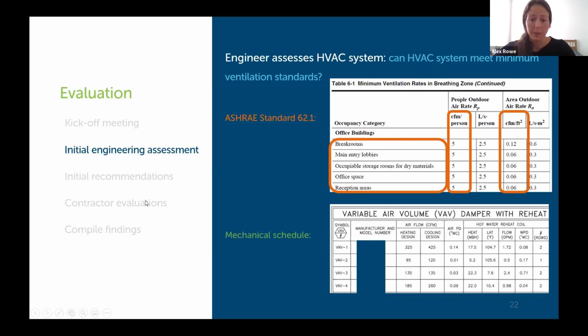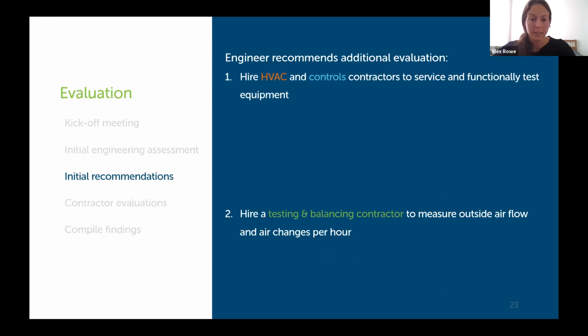Next, they reviewed the design, the as-built mechanical drawings, to see if the HVAC system, again, as designed, is capable of meeting those ventilation requirements. So they compared how much ventilation and airflow is needed in each zone as a function of area and occupants to the amount of airflow that each space was designed to have throughout the air handling units and associated VAV boxes. So that's in green right here. So at this point, the engineer's initial assessment solely looked at what was required and how the HVAC system was designed, but didn't provide much insight into what was actually going on in the building.